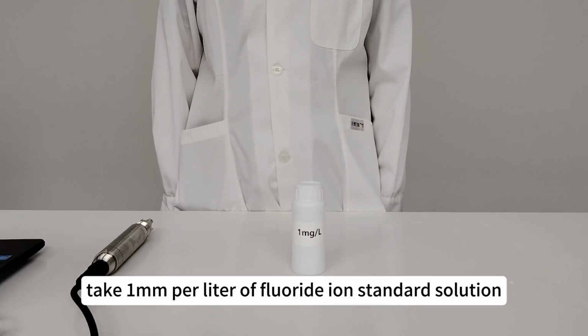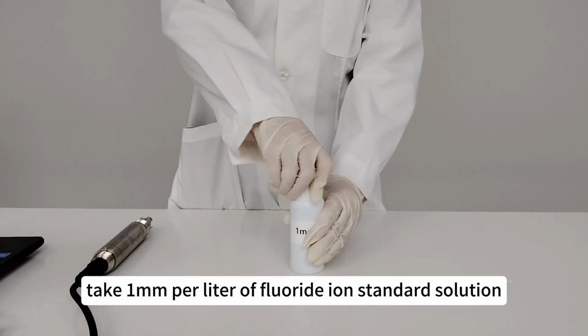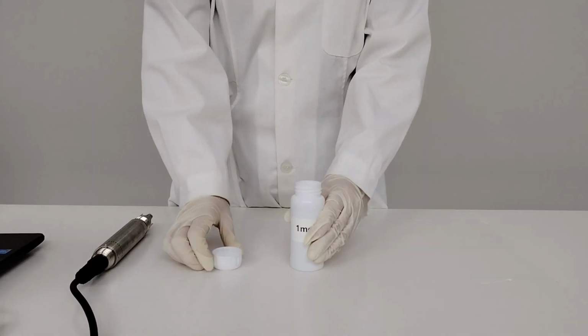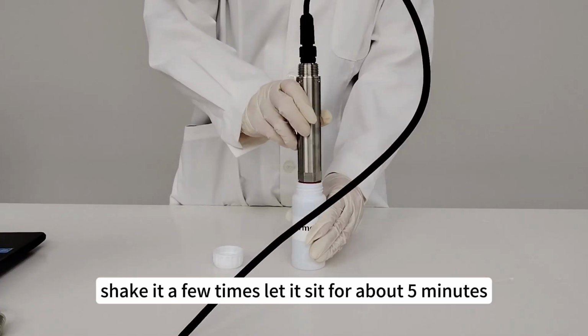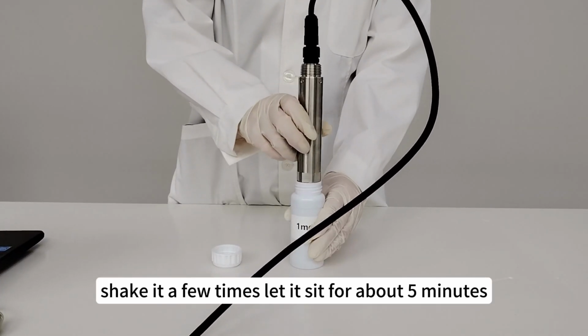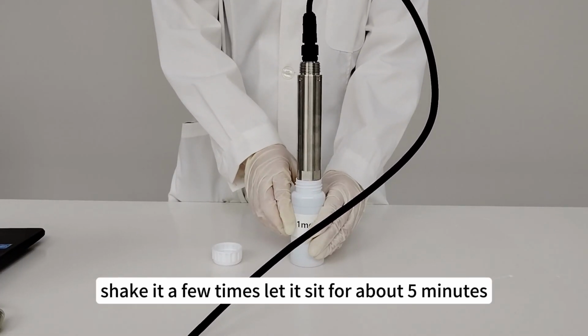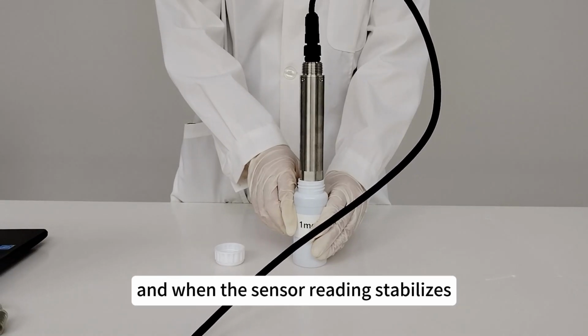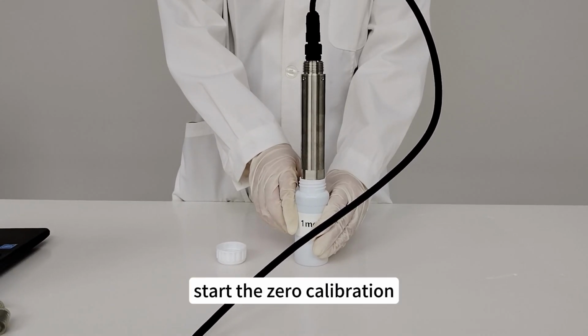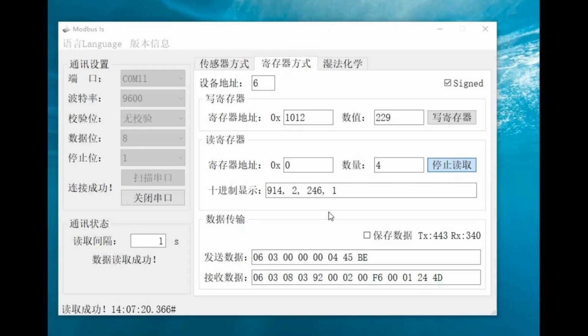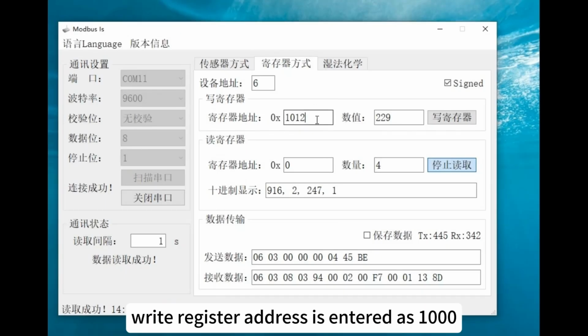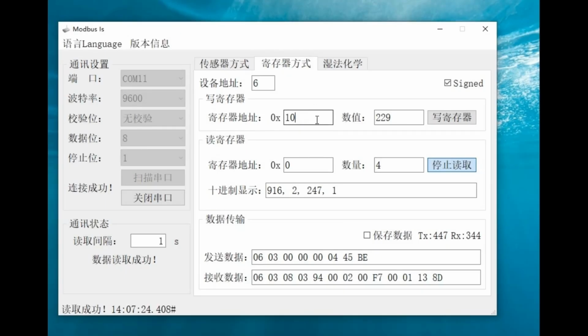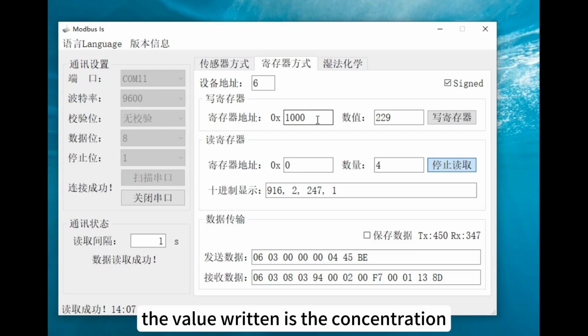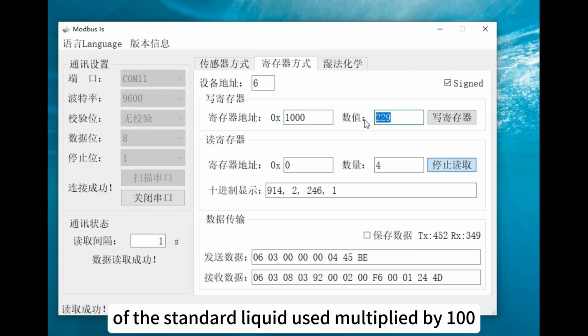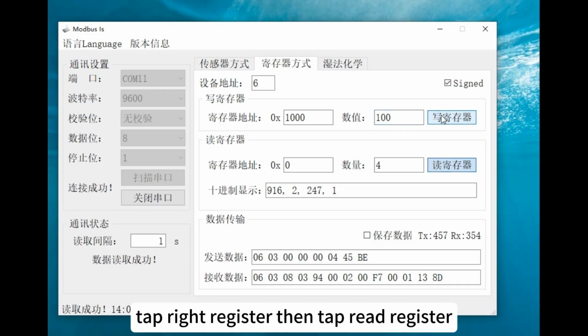For zero calibration, take 1 milligram per liter of fluoride ion standard solution. Place the sensor in. Shake it a few times, and let it sit for about 5 minutes. When the sensor reading stabilizes, start the zero calibration. Enter 1000 for the write register address. The value written is the concentration of the standard liquid used multiplied by 100. Tap write register, then tap read register.